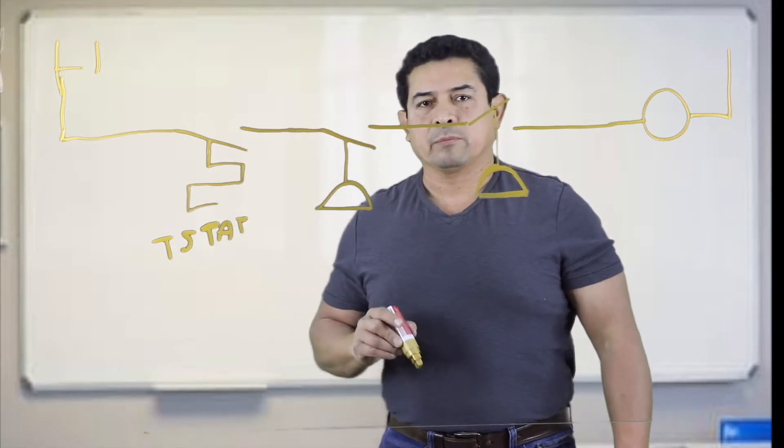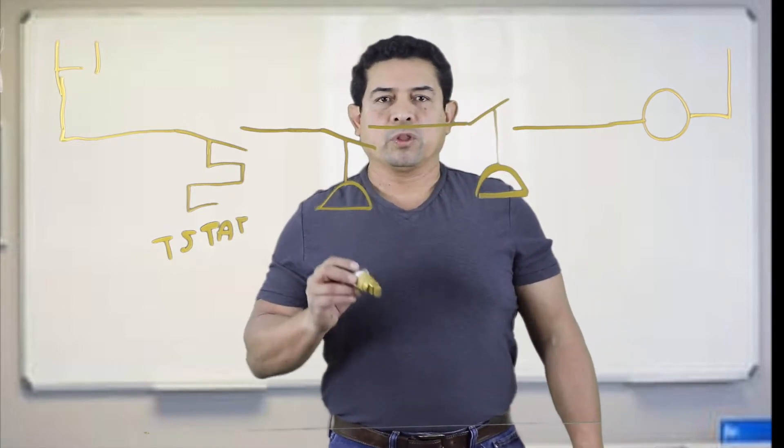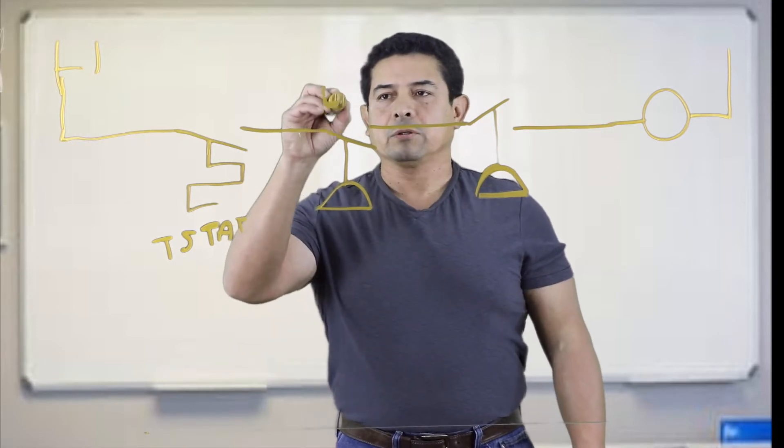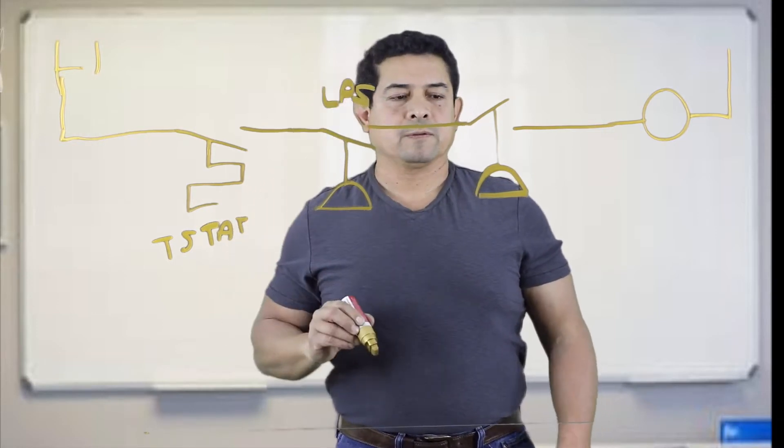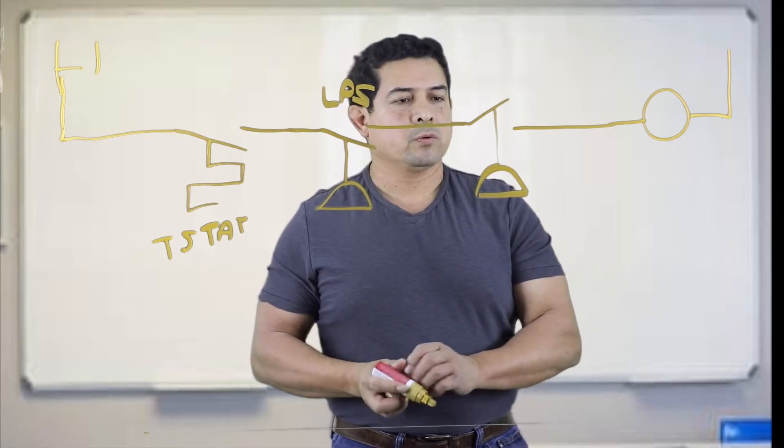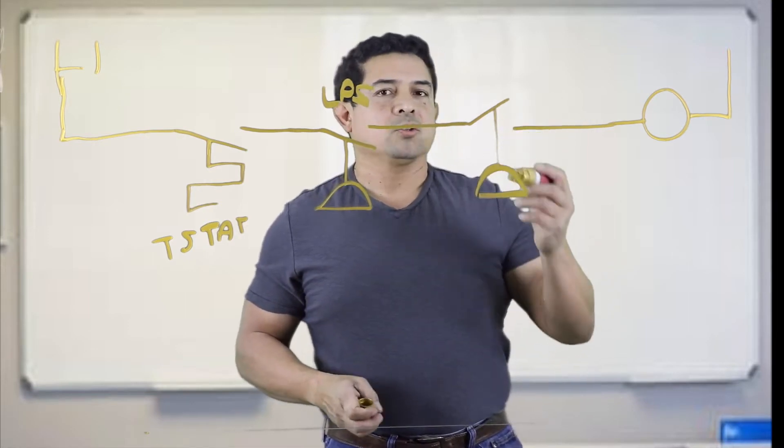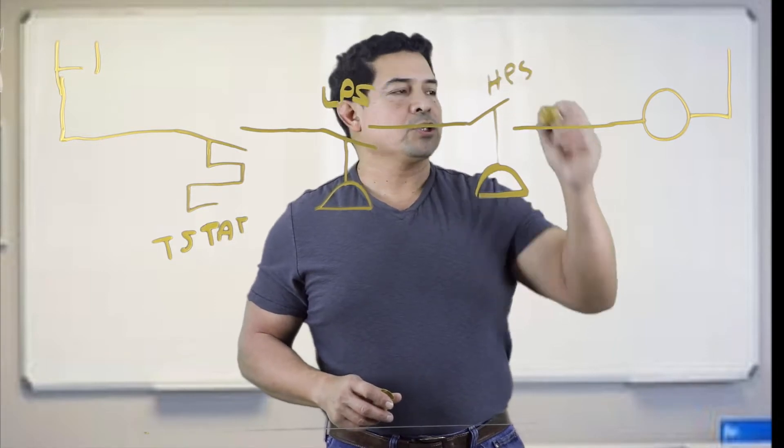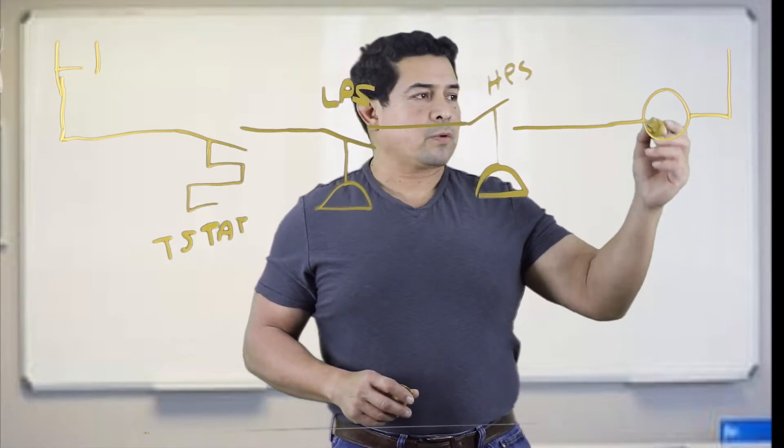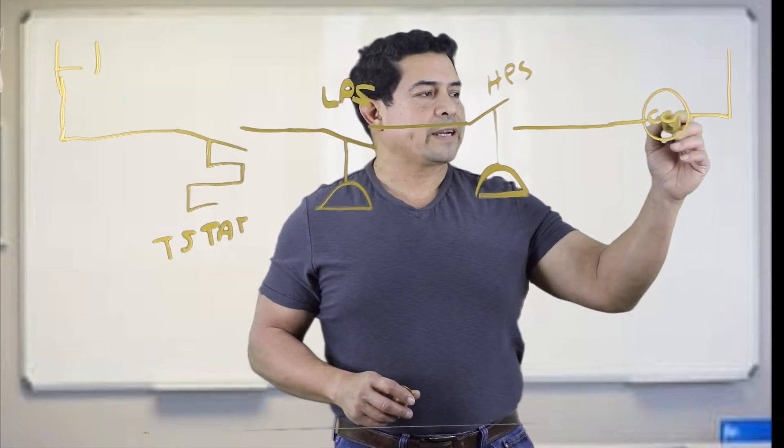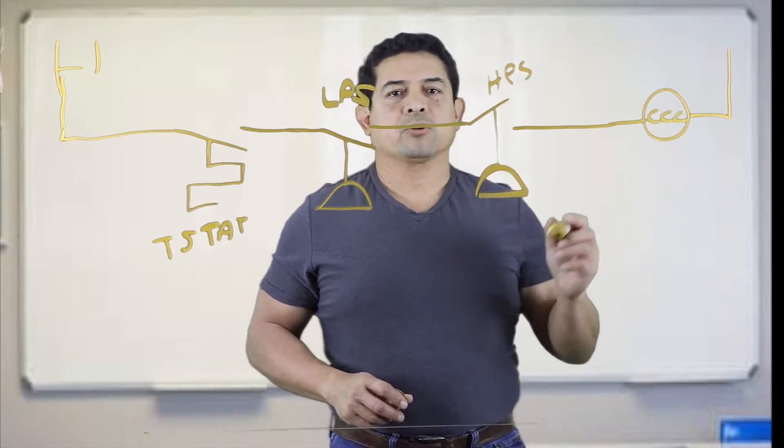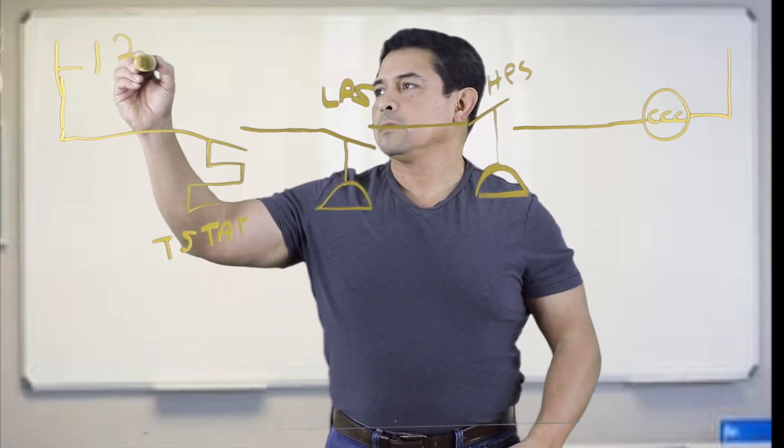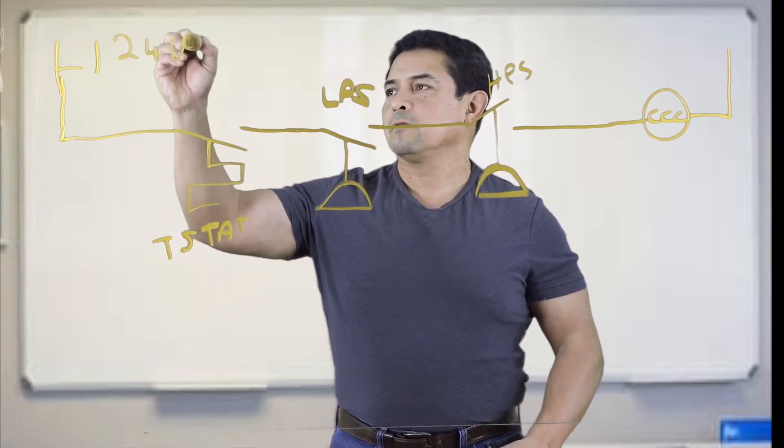So what would this one be? Pressure switch that opens when the pressure falls. Well, this would be your low pressure switch. This one is going to open when the pressure gets high. So we could say that this is going to be our high pressure switch. And this load right here, this would be your compressor contactor coil, your compressor contactor coil. So all of this, basically, is going to be 24 volts.